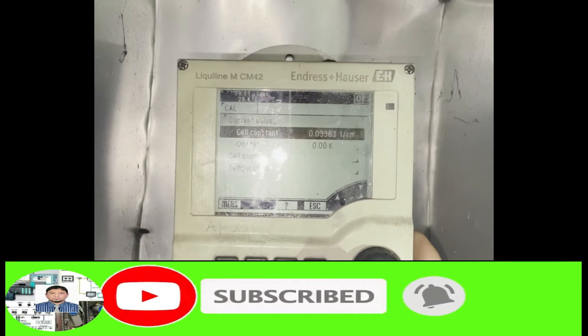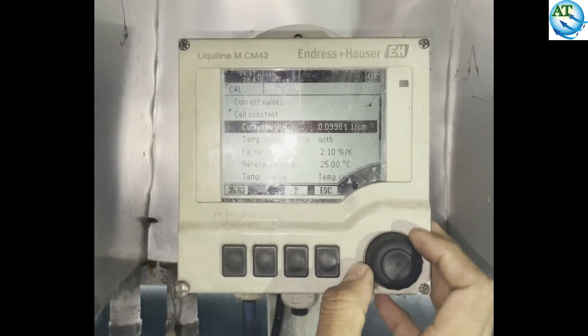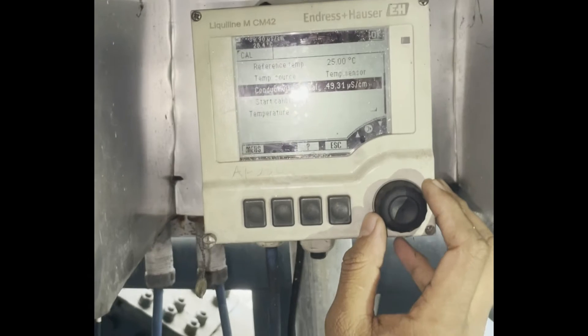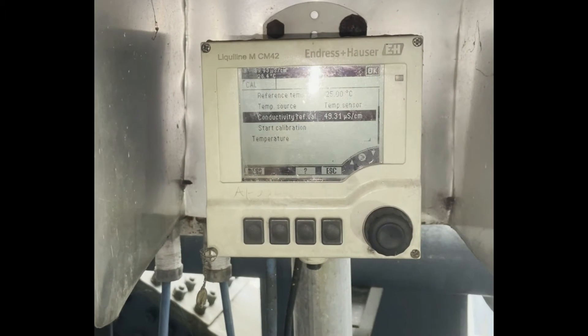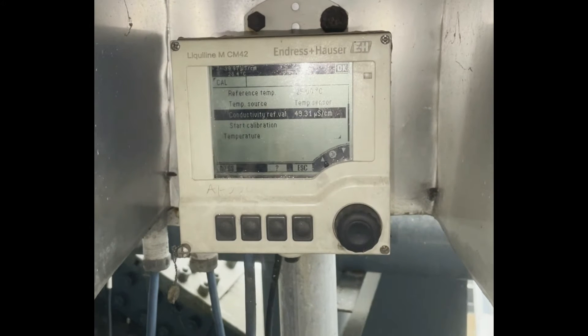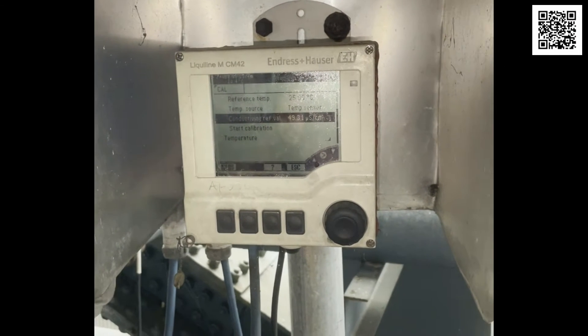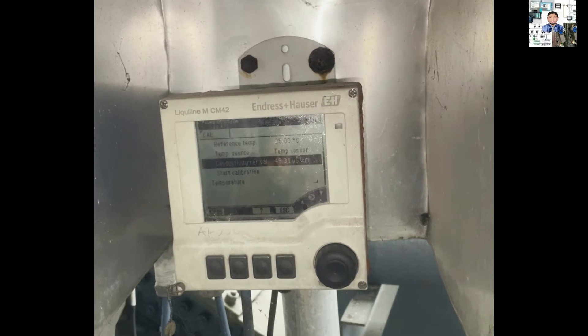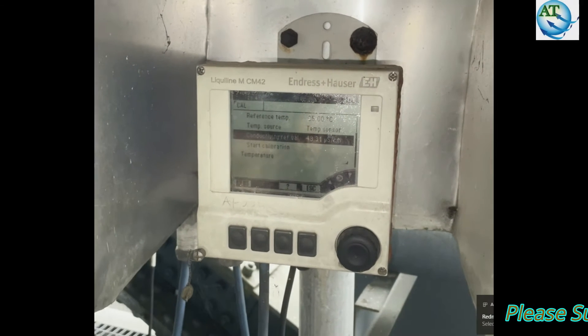In the calibration mode, when you use the calibration button, you can see the different calibration parameters fitted to the reference value. When you want to calibrate the conductivity sensor, you have to use a standard solution. The conductivity is calibrated by a reference value of 49.31 microsiemens per centimeter. That means the solution used to calibrate this transmitter or sensor had a conductivity of 49.31 microsiemens per centimeter. If you want to recalibrate this transmitter, you have to first take a standard solution with a known conductivity. Our transmitter is already calibrated, so we won't calibrate now.